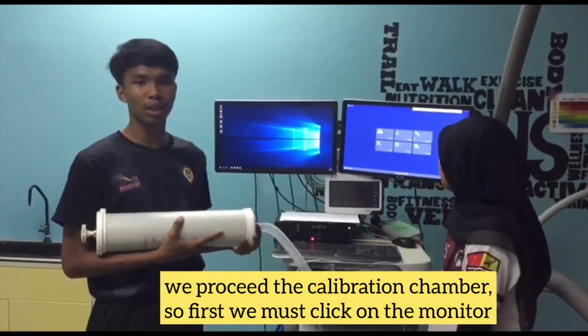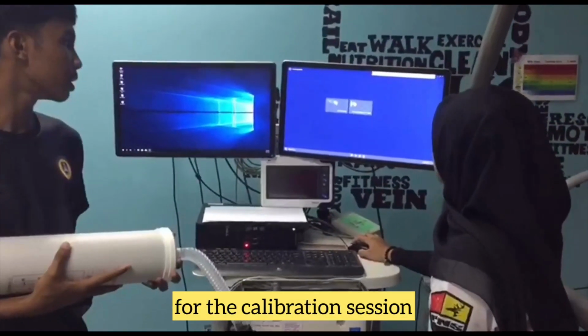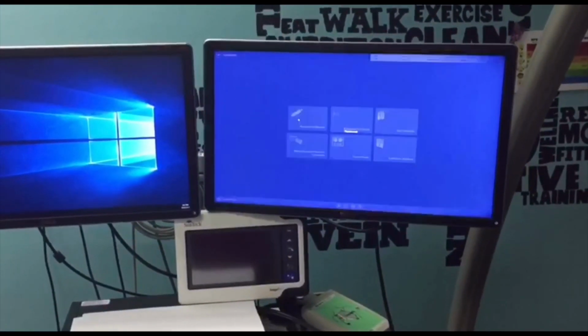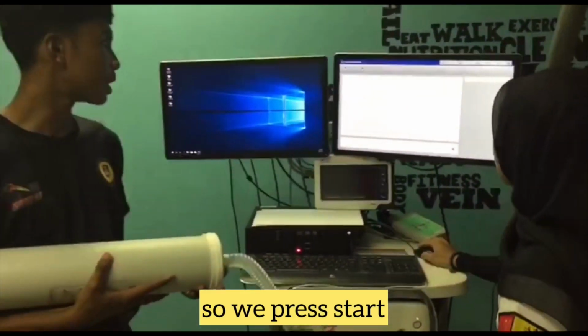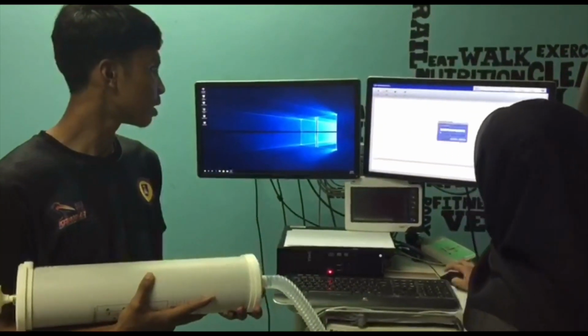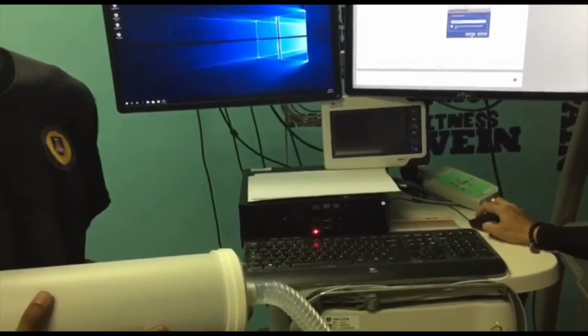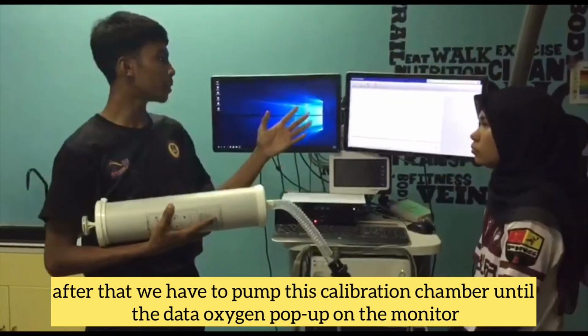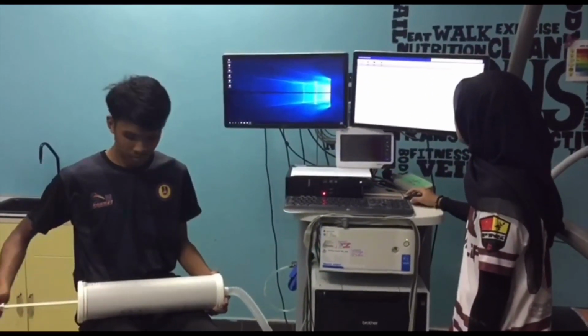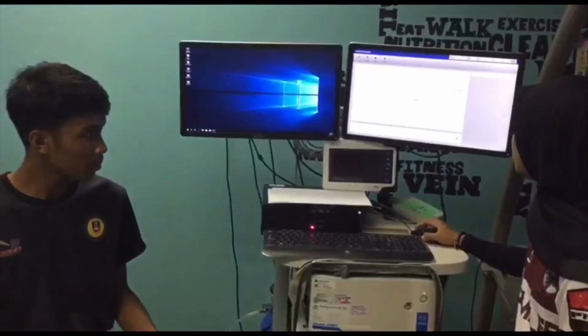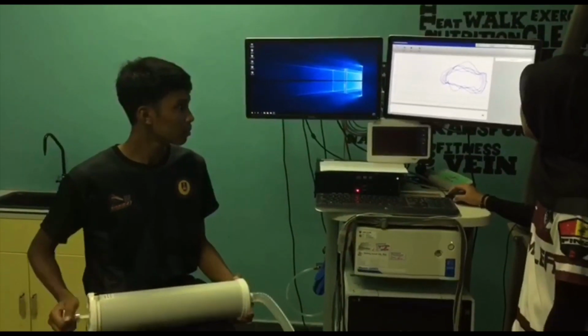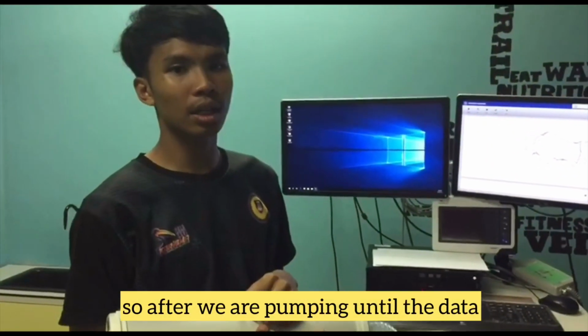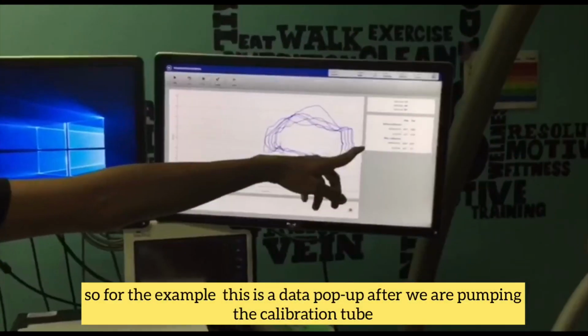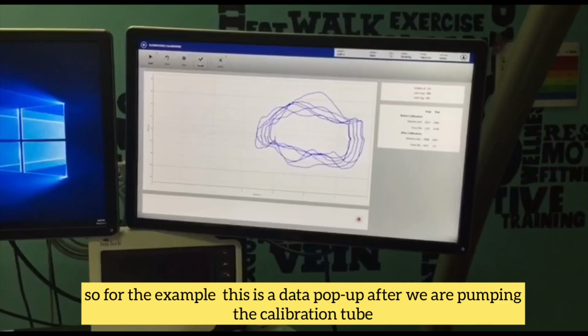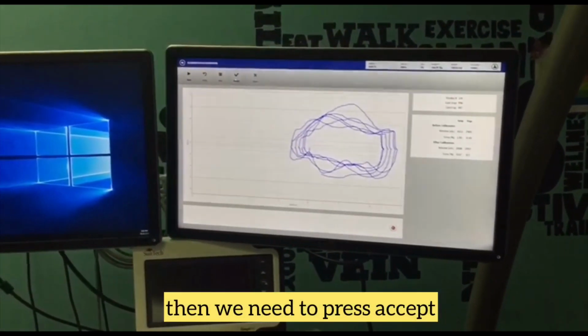So first we must click on the monitor for the calibration section. Okay, so we press start. After that, we have to pump this calibration chamber until the data of the oxygen pops up on the monitor. So for example, this is the data that pops up after we pump the calibration tube. Then we need to press accept.